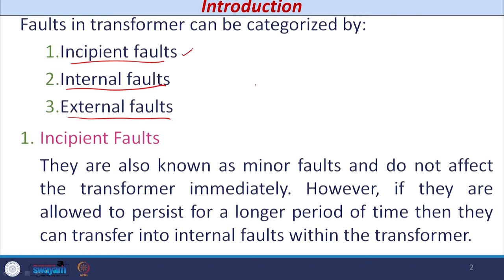Let us start our discussion with the first type, incipient faults. Incipient faults are also known as minor faults. If we wish to detect this fault, we have to use a separate device. Whenever such a fault is detected, there is no immediate need to trip the transformer. But if this type of fault persists for a longer duration, it may convert into actual electrical or internal faults of the transformer, so there is a need to detect such faults.